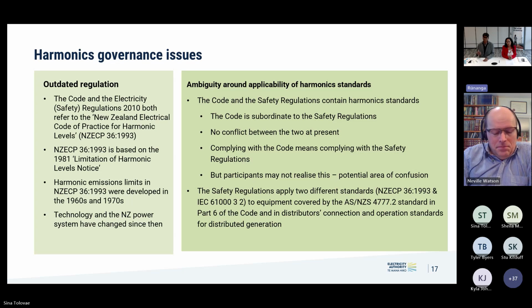The other issue is, apart from NZECP, some utilities follow AS/NZS 61000, or they might find IEEE 519 standards, because it's part of the transmission code agreement. These standards are very different, and we've found recently the issue doesn't come from a single source. If there's interaction between neighboring solar farms or BESS, there might be resonance or different impedances at the remote node. This is a big issue, and we need a uniform, whole-of-system approach to address it.